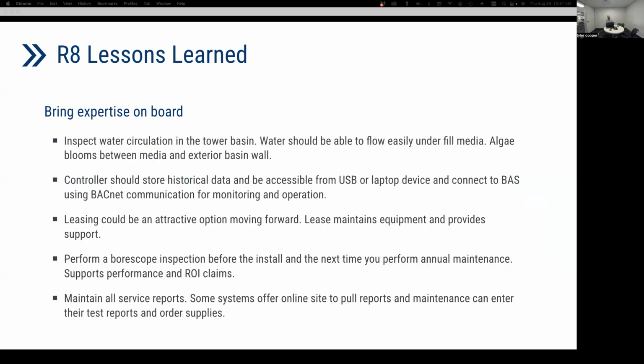So in terms of lessons learned, make sure you have appropriate expertise from your water treatment vendors. One of the critical things is water circulation in the tower basin, making sure that we're not getting algae blooms there. Whether it be water sweepers or anything else, making sure that we're getting adequate flow through those tower basins is critical.